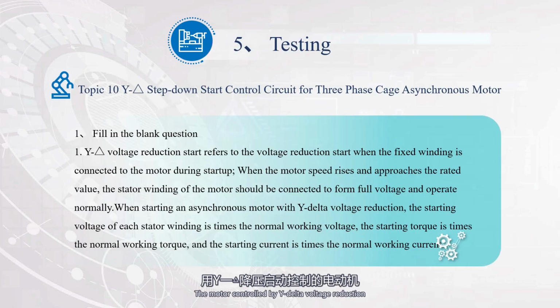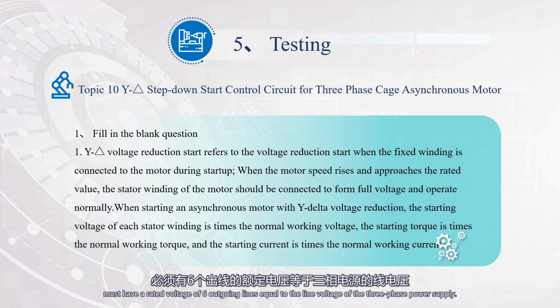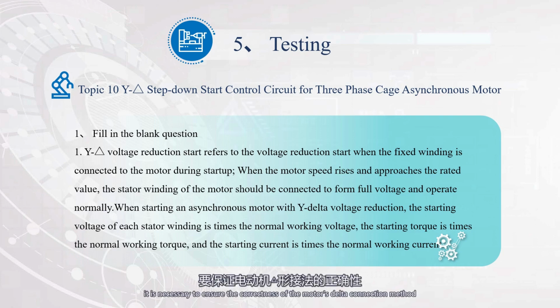Installation precautions. 1. The motor controlled by Y-delta voltage reduction must have a rated voltage, with 6 outgoing lines, equal to the line voltage of the 3-phase power supply. 2. When wiring, it is necessary to ensure the correctness of the motor's delta connection method, that is, when the main contact of the contactor is closed, it should be ensured that U1 and W2, V1 and U2, W1 and V2 of the stator winding are connected. 3. The incoming line of the contactor KMΔ must be introduced from the end of the 3-phase stator winding. If its first end is mistakenly introduced, when KMΔ is closed, it will cause a 3-phase power short circuit accident.